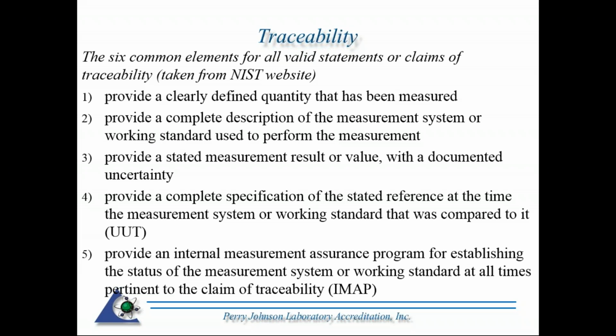Number 2, a complete description of the measurement system or working standard used to perform the measurement. So what did the non-accredited source use for comparison? That would need to be known. However, it would also need to be verified. So the objective evidence brought forth here would be that the organization would have to go to the supplier. They would need the report for the instrument that was used to calibrate your instrument. If that was done by an accredited source, it's an accredited report. If everything's in line there, then the buck hopefully would stop there. If not, then this will snowball over to the next organization down the line. So, for example, with the micrometer, let's say it was ceramic gauge blocks. That would need to be stated on the report, identify that report. Then we would also need to see the traceability that comes with that.